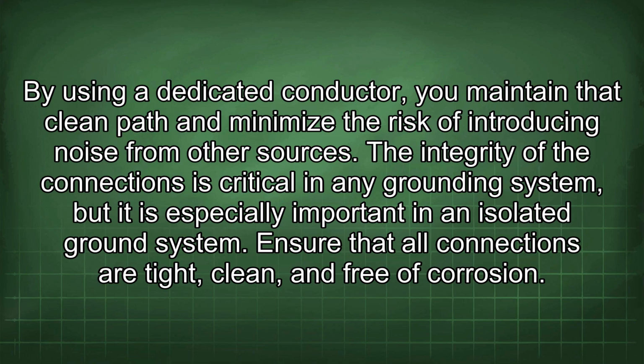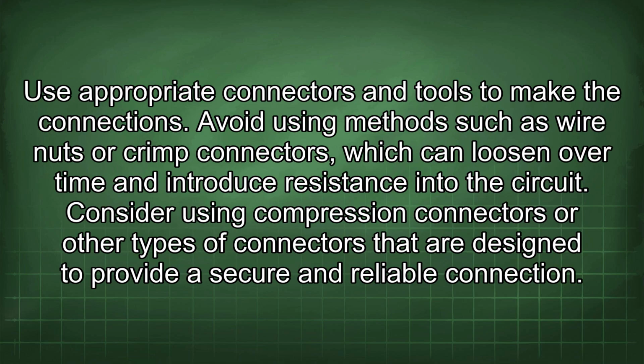The integrity of the connections is critical in any grounding system, but it is especially important in an isolated ground system. Ensure that all connections are tight, clean, and free of corrosion. Use appropriate connectors and tools to make the connections. Avoid using methods such as wire nuts or crimp connectors, which can loosen over time and introduce resistance into the circuit. Consider using compression connectors or other types of connectors that are designed to provide a secure and reliable connection.